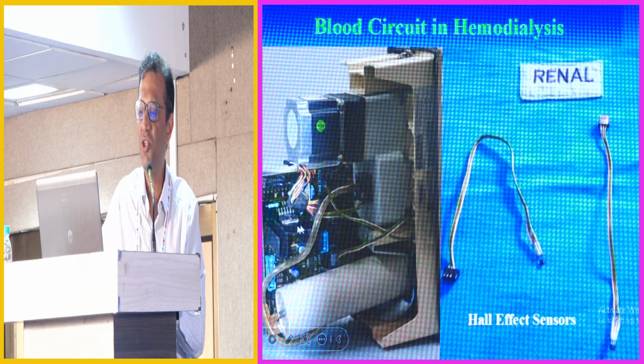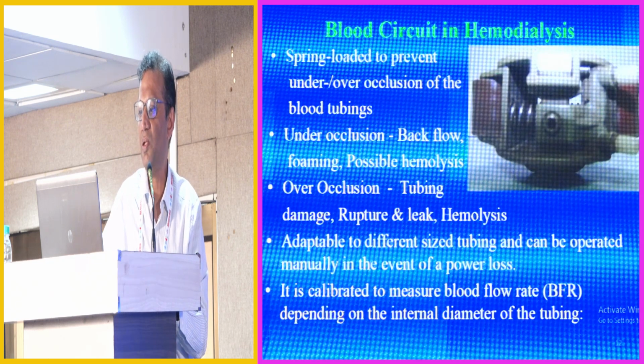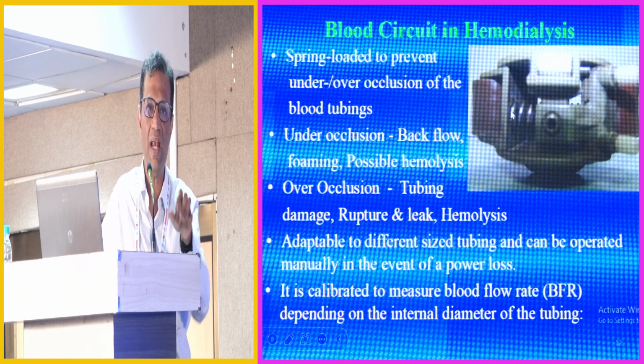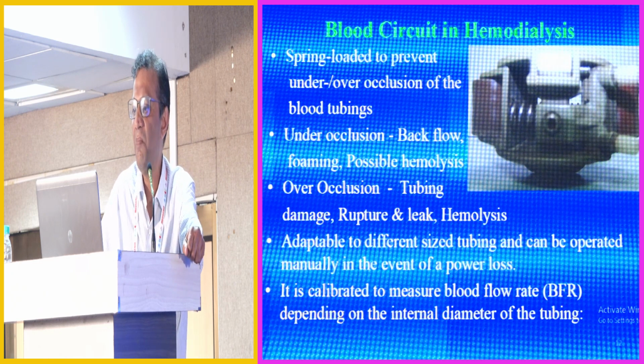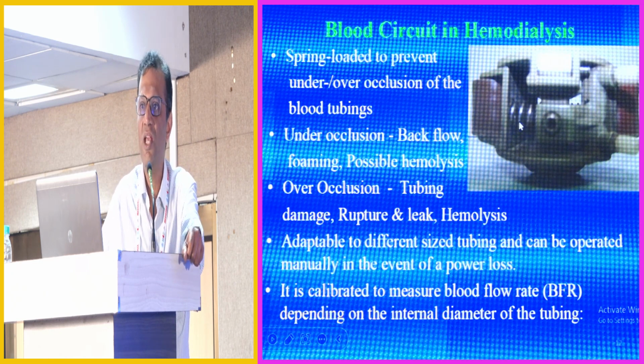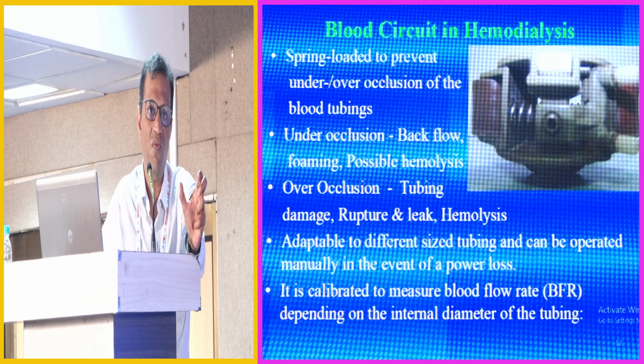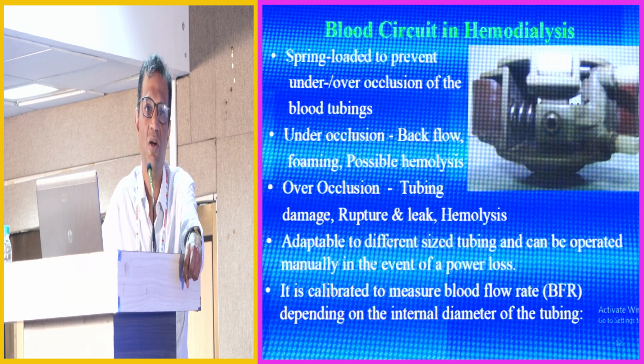And you can also see this tubing inside, which connects to the arterial pressure port and then to a strain gauge sensor within the machine. Now this is what the roller pump looks like. There are 2 rollers here, these brown things, and the rollers are maintained at a fixed distance from the stator by the tension in a spring over here. In most of our dialysis circuits, our tubings have an occlusion diameter of about 6.4 mm. The 5008 uses dedicated pump segments which have an occlusion diameter of 8 millimeters.